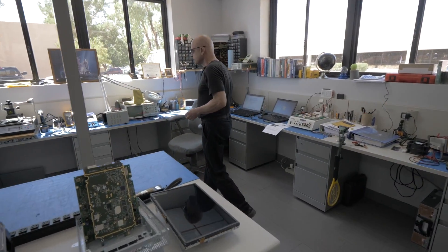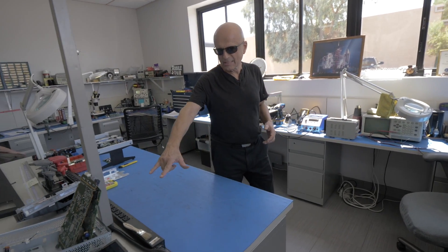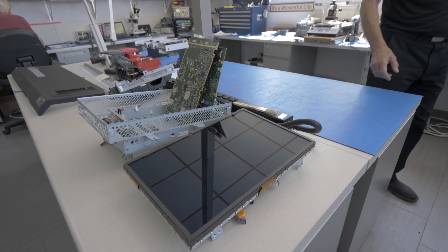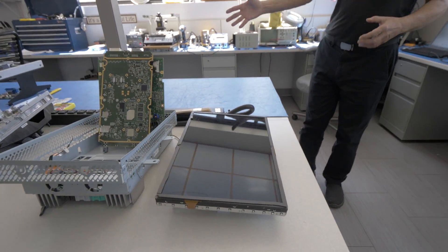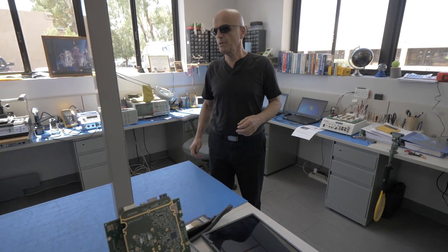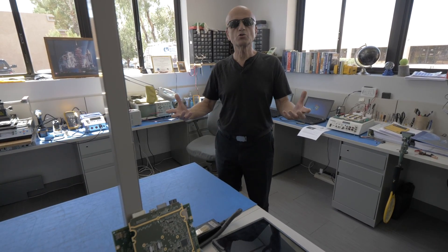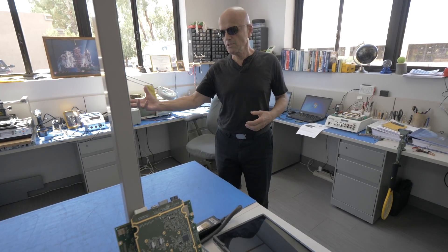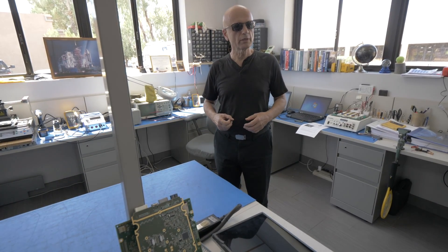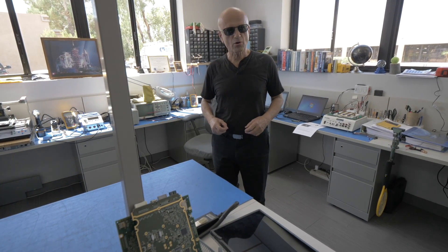The rest of this operation is repairing UPS power modules. It looks like we're doing nothing but EV today. This is a Tesla Model S MCU stack — we work on those as well. Normally they would have UPS modules here, and that's what got us in this business. We've been repairing UPS's for about 36 years. It's the same technology as what is found in these electric cars: DC plant inverter, three-phase or single-phase. In a UPS the difference is what it powers — in a car you're driving a motor, in a data center you're powering servers and computers.